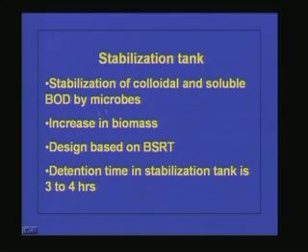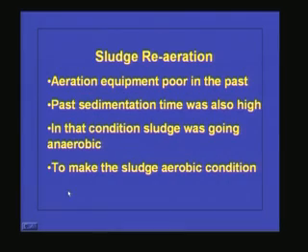So naturally there is an increase in biomass concentration, and the stabilization tank of the contact stabilization process is designed the same way as the aeration tank of the conventional activated sludge process. That means the design is based on BSRT. Detention time in the stabilization tank is 3 to 4 hours, or sometimes it goes up to 8 hours.